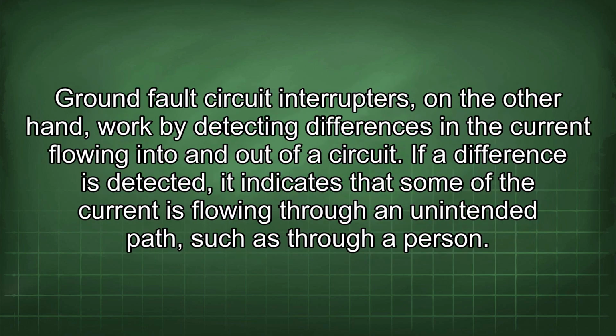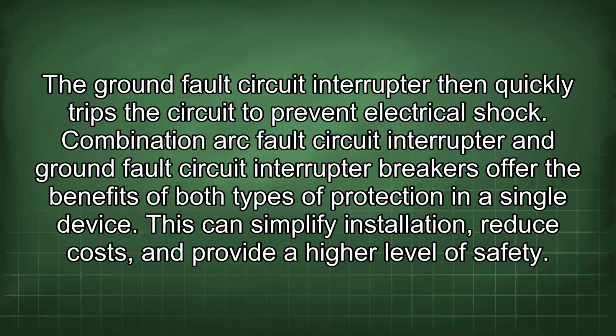Ground fault circuit interrupters, on the other hand, work by detecting differences in the current flowing into and out of a circuit. If a difference is detected, it indicates that some of the current is flowing through an unintended path, such as through a person. The ground fault circuit interrupter then quickly trips the circuit to prevent electrical shock. Combination arc fault circuit interrupter and ground fault circuit interrupter breakers offer the benefits of both types of protection in a single device. This can simplify installation, reduce costs, and provide a higher level of safety.